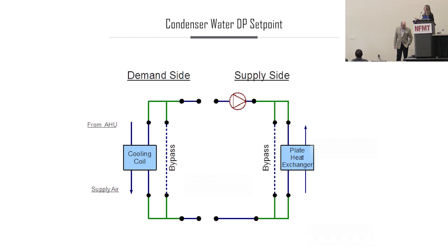So we implemented a program where we said, okay, we want it to be a 10 degree delta. If it's greater than 10 degrees, let's speed that pump up. If it's less than 10 degrees, let's slow it down to try to maintain that. So that's for a condenser water loop that we did that for, but if you have a pump in any system that is running at a constant DP, then you're able to do this. It's pretty snazzy, I think.